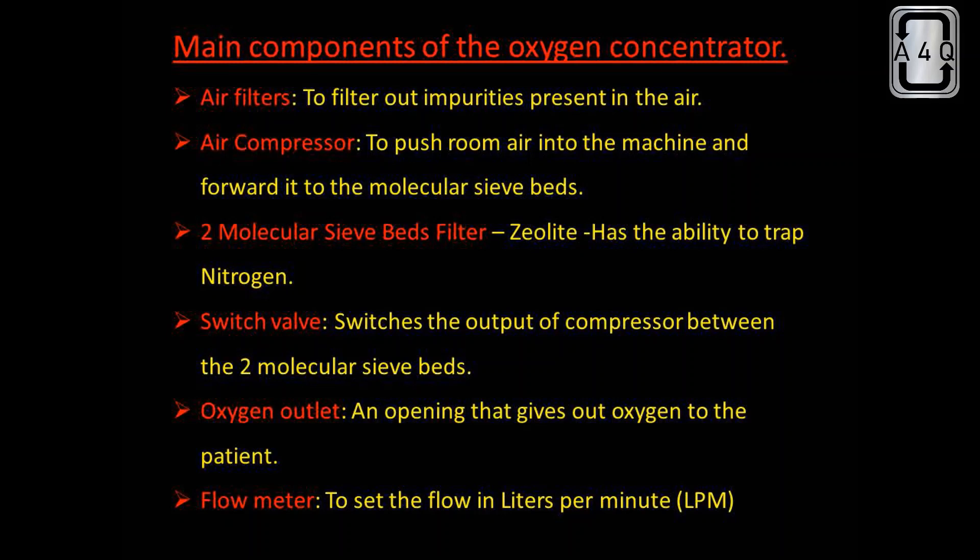Main components of the oxygen concentrator: Air filters to filter out impurities present in the air. Air compressor to push room air into the machine and forward it to the molecular sieve beds.